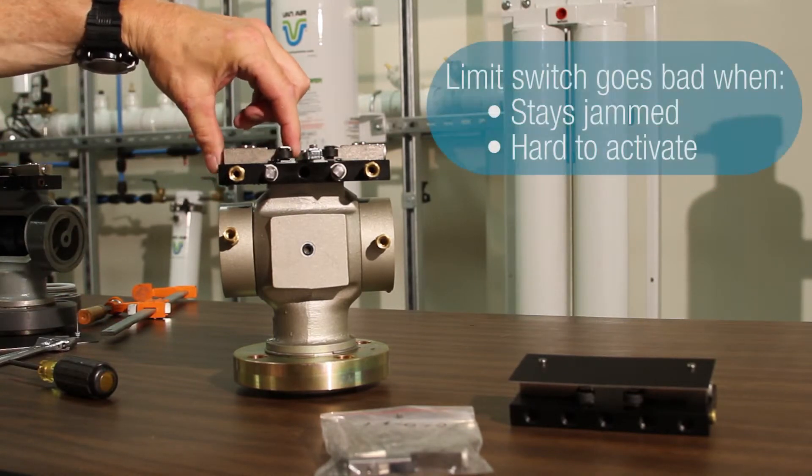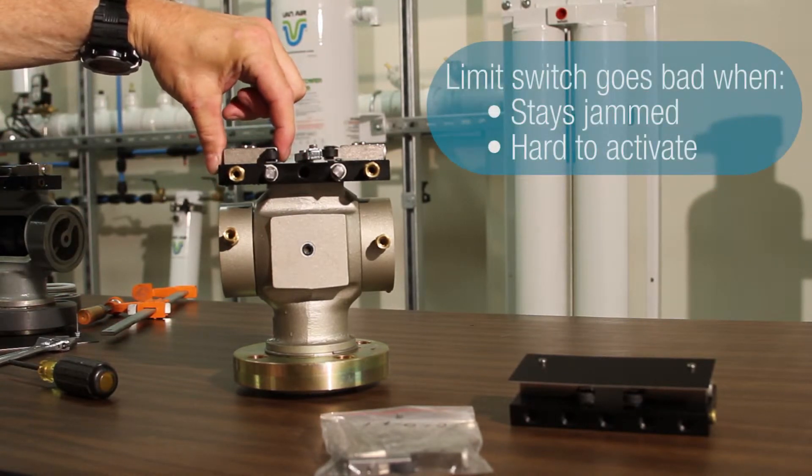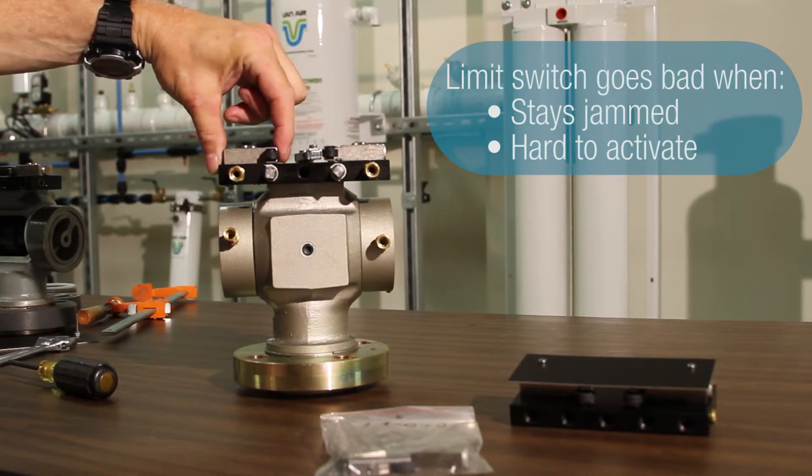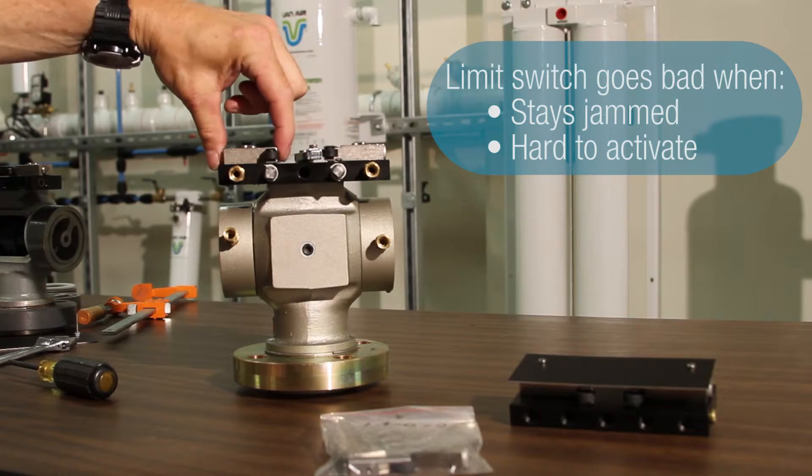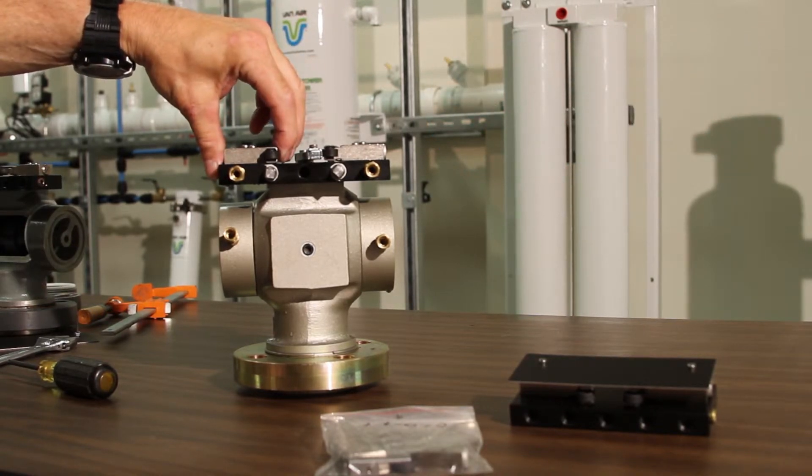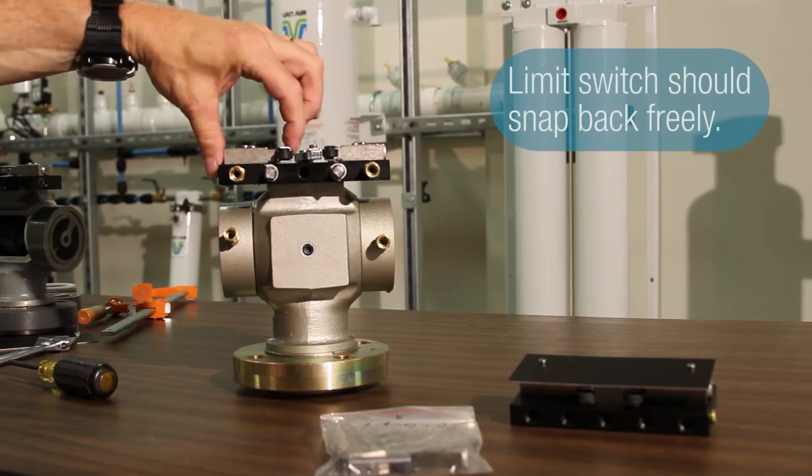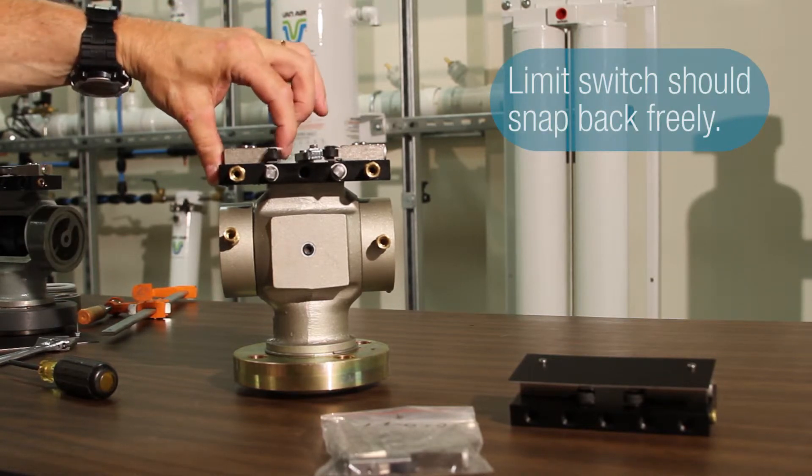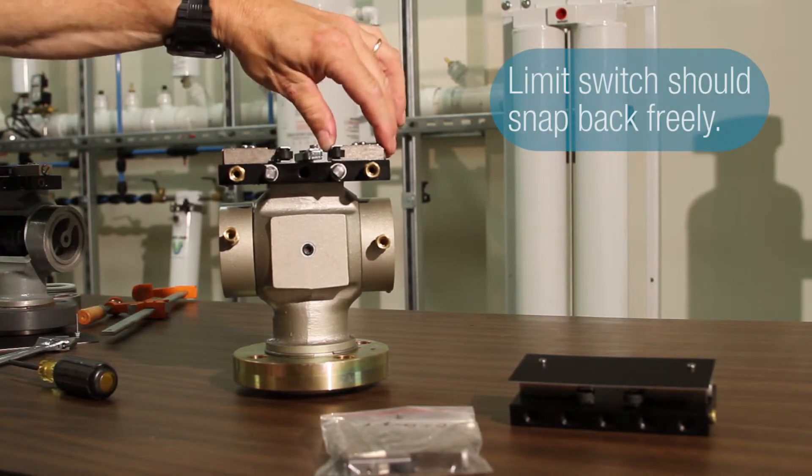Now, normally if a pneumatic limit switch goes bad, it's either going to stay jammed in the activated position, or it'll become very hard to activate. The switch should activate freely to the activated position and snap back by itself. So you should be able to see it snap back freely.